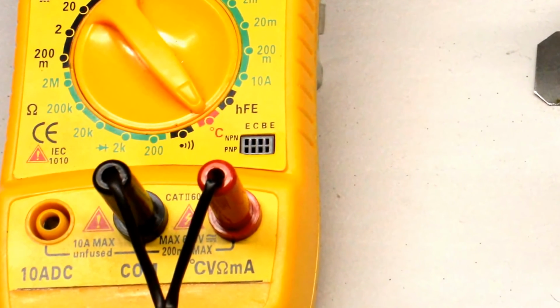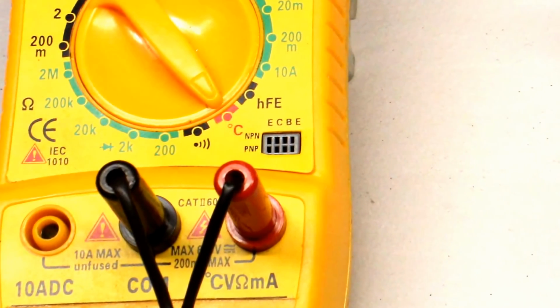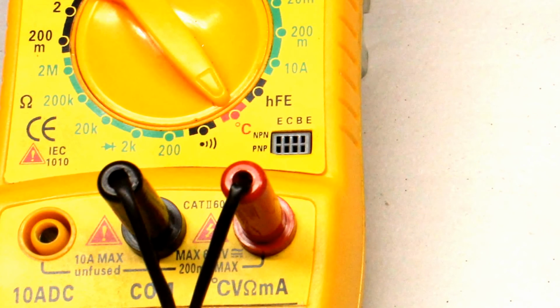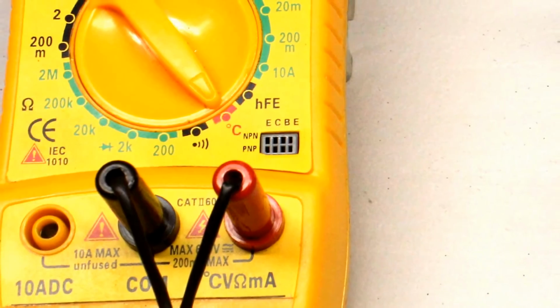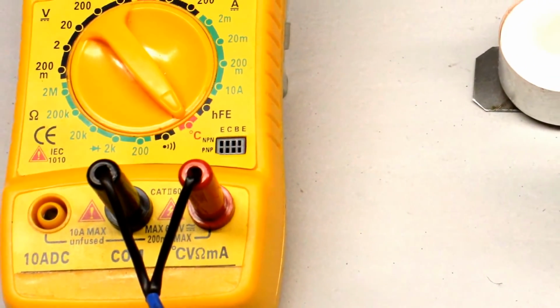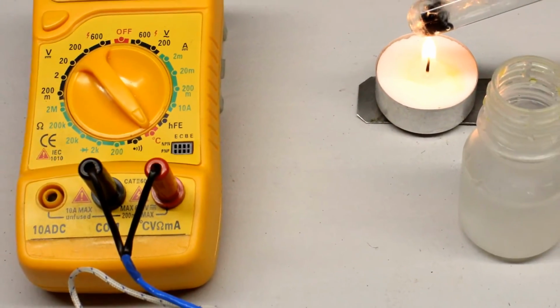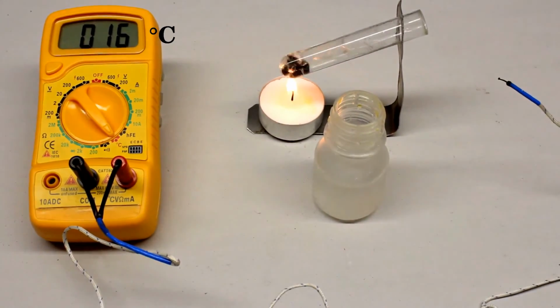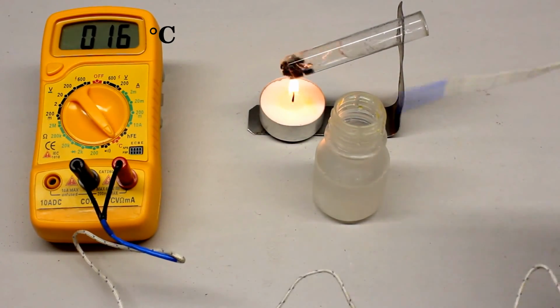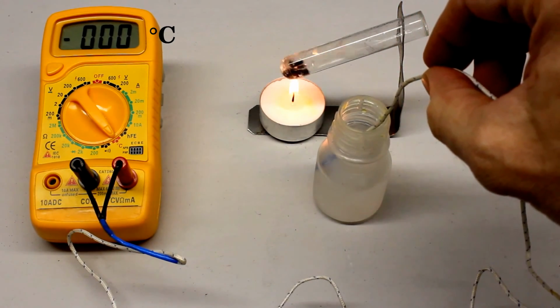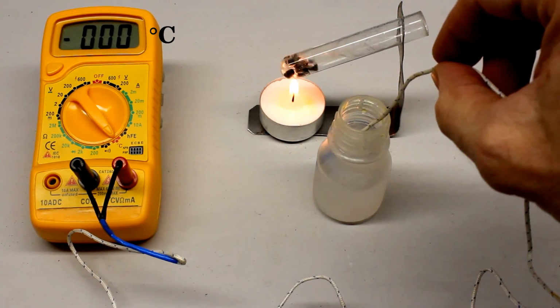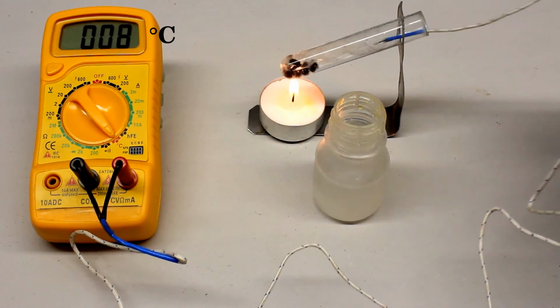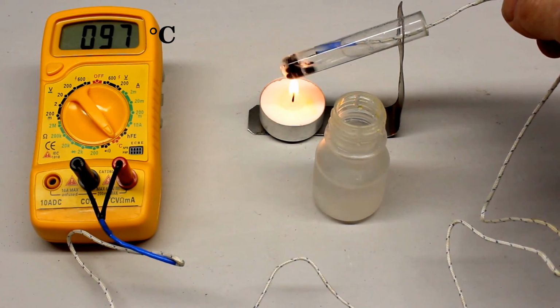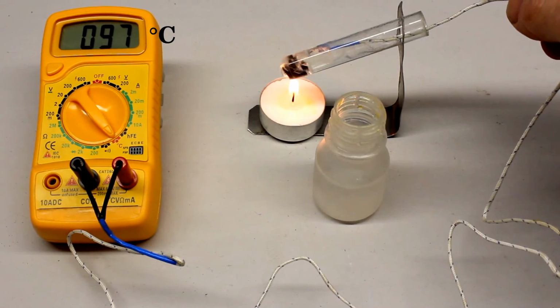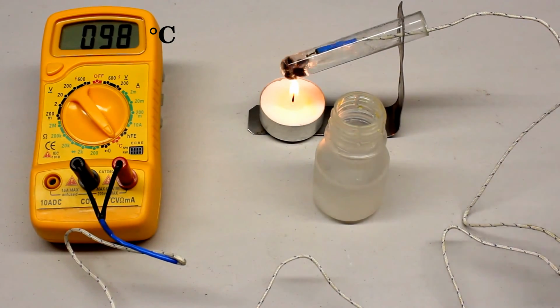The test leads have to be replaced by a thermocouple and the rotary switch has to be set to the temperature function. According to the instruction manual, the multimeter is capable of detecting temperatures ranging from -20 to +1000 degrees Celsius. Water with some ice has a temperature of 0 degrees Celsius and the multimeter indicates exactly 0 degrees Celsius. The temperature of boiling water is indicated with 98 degrees Celsius, however that value depends on the atmospheric pressure.